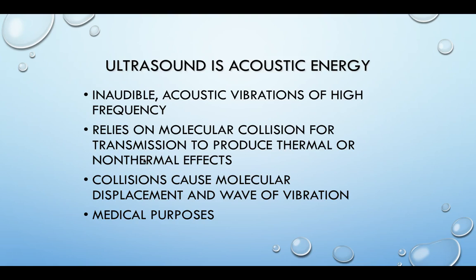Lower frequencies of ultrasound energy tend to have greater depth of penetration, while higher frequencies are a little more superficial. Our one megahertz can get up to about six centimeters deep, while three megahertz — which are typical settings for our ultrasound — can penetrate about two to three centimeters deep.